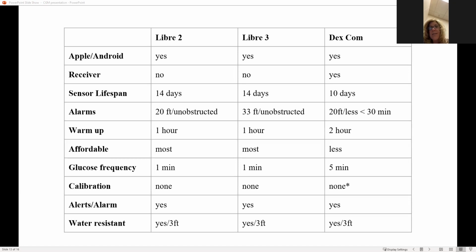Calibrations, there are none. The reason I have Dexcom, I have a little asterisk there, is there is a code that the patient needs to make sure matches on their transmitter. And as long as it matches, there's no calibrations needed. So calibrations are when they have to do blood finger sticks and basically enter them into a system to get the CGM to line up more accurately. So there is none anymore for Libre 2, 3, or the Dexcom. I've already said that they all have alarms and alerts, and they are water resistant. So showering is fine. Getting into pools for short periods of time are fine, and they are tested up to 3 feet. Next slide.